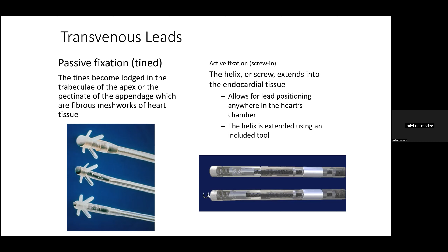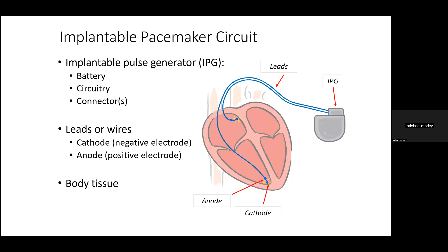Put them together and put them in a patient, and you've got the pacemaker circuit consisting of the generator, the leads, and the patient's tissue. And depending on how many leads you put in, you can have different kinds of pacing systems. So the simplest pacemaker system, which would sort of mirror our temporary pacing wire system, would be a single chamber ventricular pacemaker.